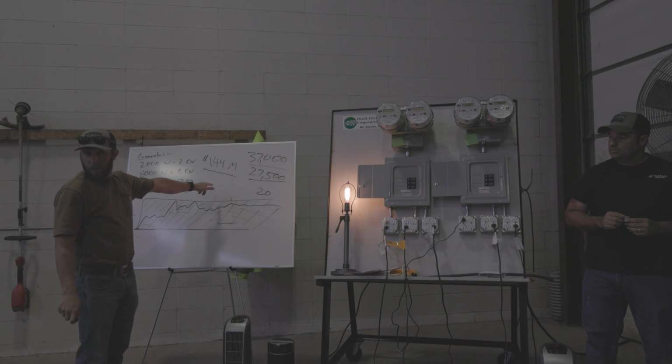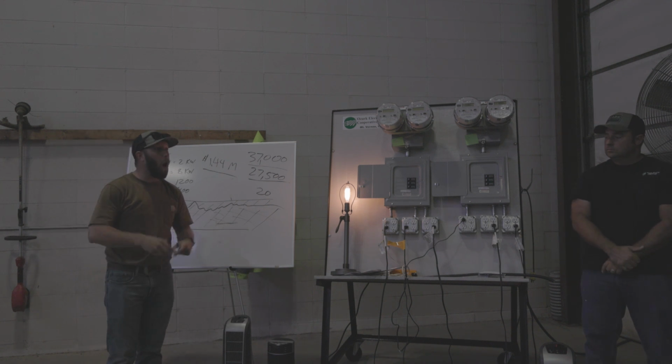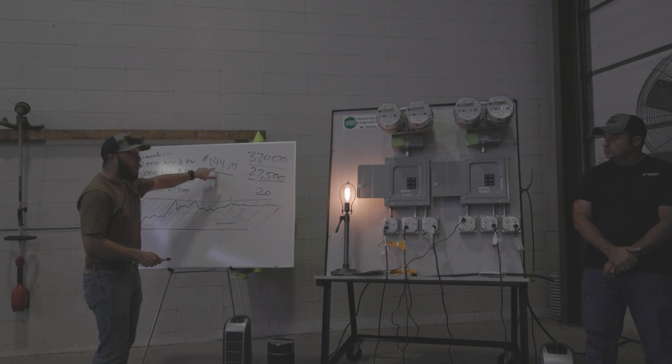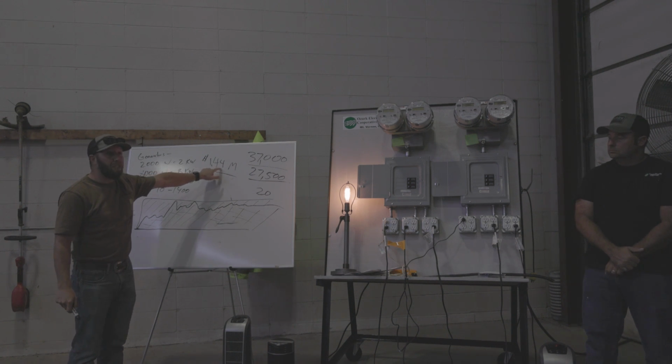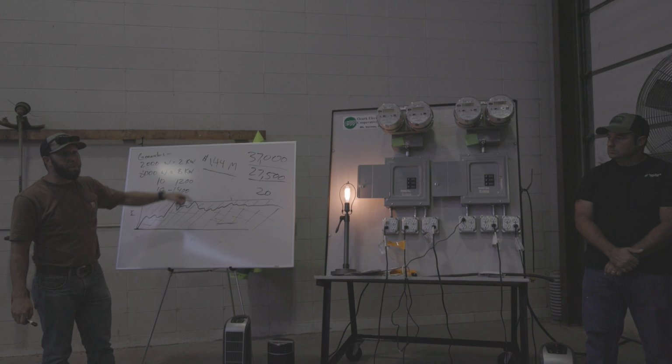If we all peak together, that's what sets our peak billing determinant on our demand. So all of a sudden the co-op has a demand that we're going to pay all of us collectively. That's this $1.44 million, right? That's the number that we're going to be stuck collecting for the next 12 months to try to cover the demand if we're all peaking together at a certain time.